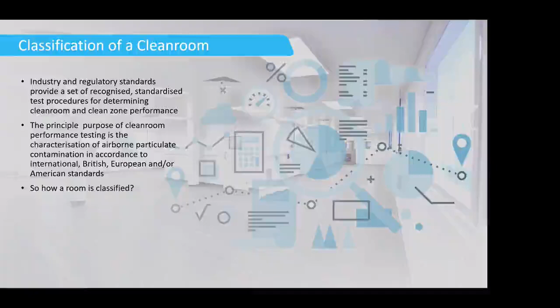So to give an idea of the kind of particles we're talking about, human hair sits around the 80 micron range. The size particle you can see is around the 40 to 50 micron range. We're working all the way down in the sub-micron range, 0.1 to 0.3 microns: smoke, bacteria, viruses. These are the things we're very keen on filtering out of the air.